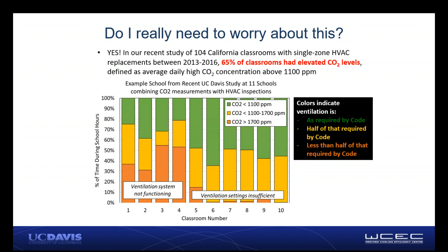What we ended up finding was that 65% of classrooms had elevated CO2 levels, even though they had recently purchased new equipment and had it installed, and generally thought everything was working well. The colors here on this bar chart are just one example school that we went to. We also inspected the HVAC system to identify some of the reasons why the systems weren't working. You can see in 4 classrooms, the ventilation system was not functioning at all, and the orange bars suggest that's less than half of the ventilation required by code. And 6 of the classrooms had a working ventilation system, but it wasn't configured correctly, so it wasn't providing a high enough ventilation rate. Next slide.